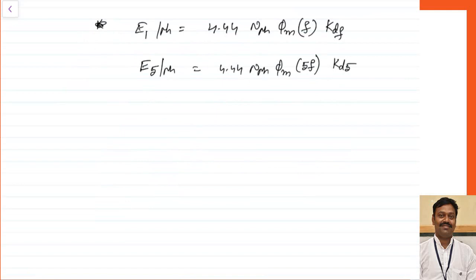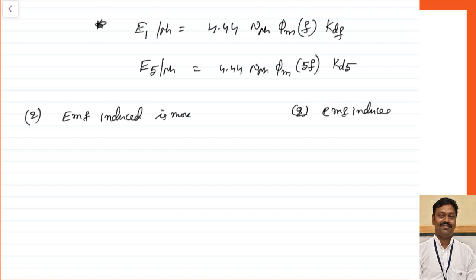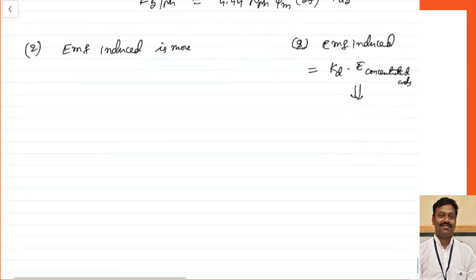The major difference between concentrated and distributed winding: in the case of concentrated winding, the EMF induced is more — equal to the full formula — whereas in distributed winding, EMF is less than that of concentrated winding because it is multiplied by Kd, the distribution factor.